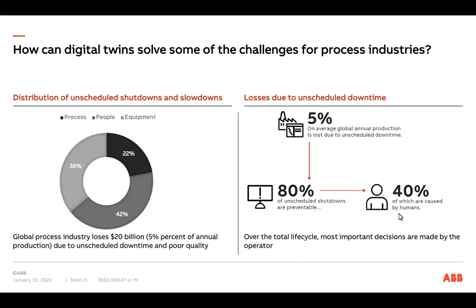ABB actually has a kind of hidden gem of a digital twin in its control system, called an aspect object. What that means is that for every object you have on the plant, for example a motor, it has a digital twin aspect object that contains all the information relevant for that device, for the operator, the engineer, or maintenance personnel. So you can have one place where all information is accessible, for example alarm limit configuration.